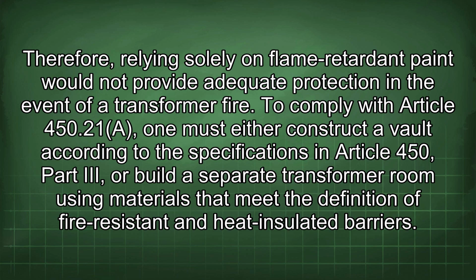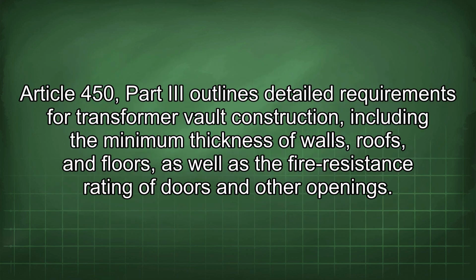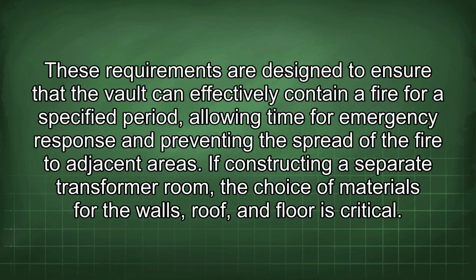To comply with Article 450.21a, one must either construct a vault according to the specifications in Article 450, Part Roman 3, or build a separate transformer room using materials that meet the definition of fire-resistant and heat-insulated barriers. Article 450, Part Roman 3 outlines detailed requirements for transformer vault construction, including the minimum thickness of walls, roofs, and floors, as well as the fire resistance rating of doors and other openings. These requirements are designed to ensure that the vault can effectively contain a fire for a specified period, allowing time for emergency response and preventing the spread of the fire to adjacent areas.